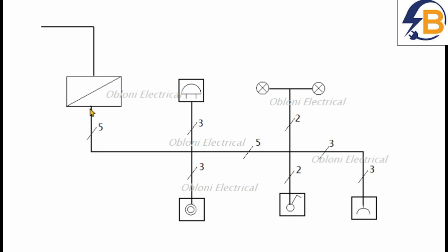In this case, the three wires coming here will have two feed wires and then one switch wire to the bell — so already three of these five cables are going to the socket. Then we have one coming to the bell switch, and we loop from the bell switch to the one-gang switch. So here we have two feed wires — the one from the board and the looped one — plus another wire to operate the bell. The other wire here will be a neutral that serves the bell, and we loop from here to the lamps.